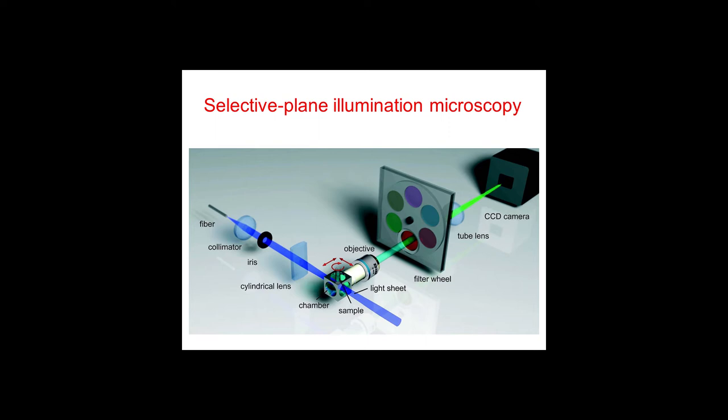So, essentially, the SPIM is a microscope where the objective is perpendicular to the light source, so essentially you have a laser that is collimated, and then you have a cylindrical lens that creates a sheet out of the laser, of the punctiform laser source. And now the sheet essentially makes an optical section through the tissue, but you are recording it at 90 degrees, that is, you are making an image of everything that is illuminated by your laser source. And this is why it's also called light sheet microscopy.